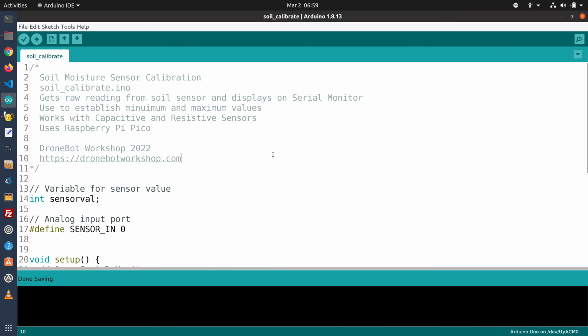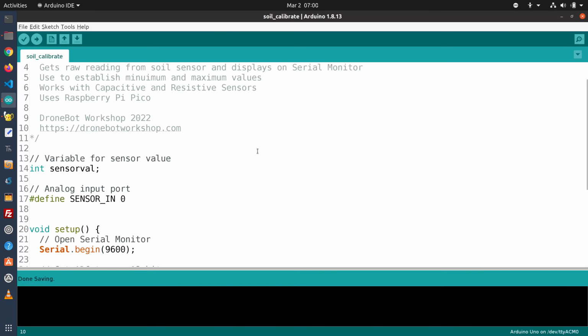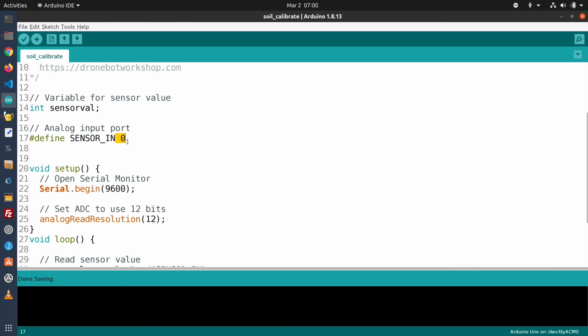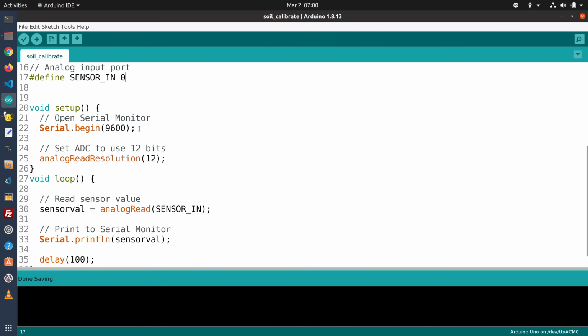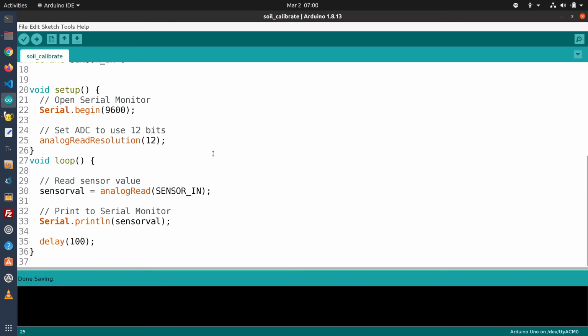Here's the sketch we're going to use to calibrate our sensors, and we can use this with both capacitive and resistive sensors. It's an extremely simple sketch. We start by defining a value to get the sensor value, which is the output of the analog to digital converter, and then we define the ADC pin itself, which is ADC0. Then we open up our serial monitor so we can see our results. We also set our analog to digital converter resolution to 12 bits. If we don't do this, it'll default to 10 bits, and we want to get all the resolution we can.